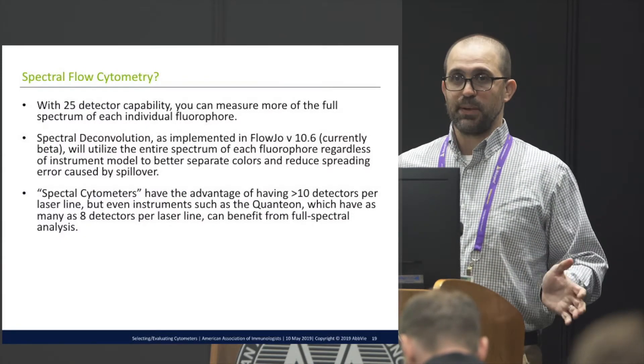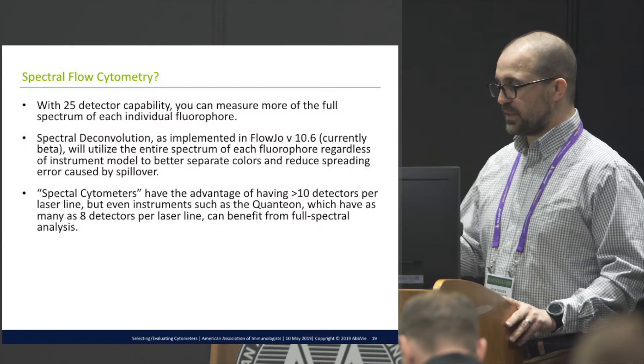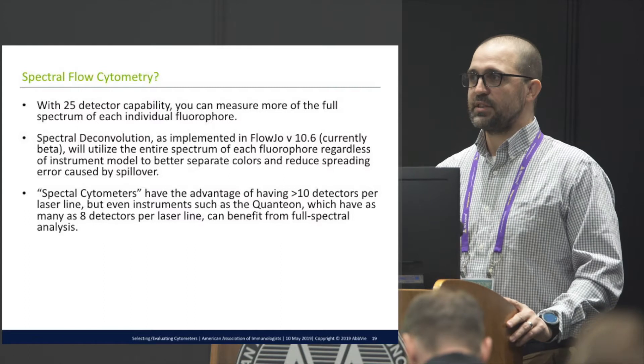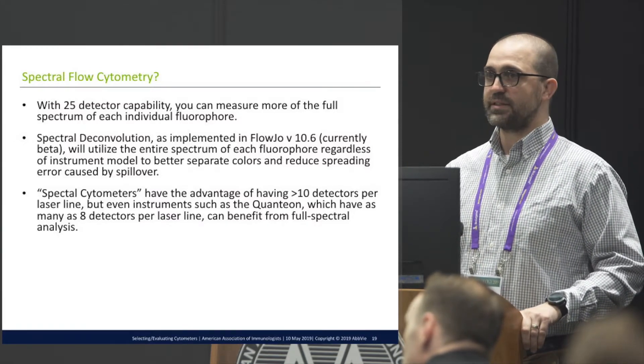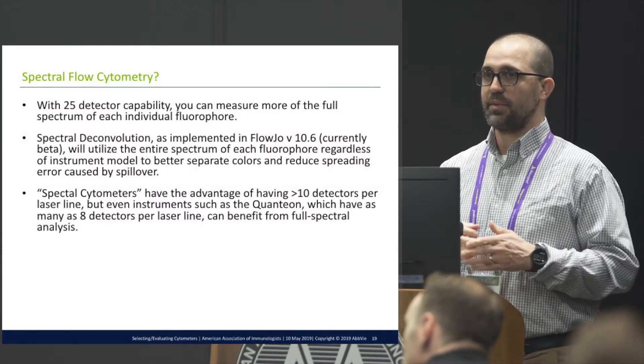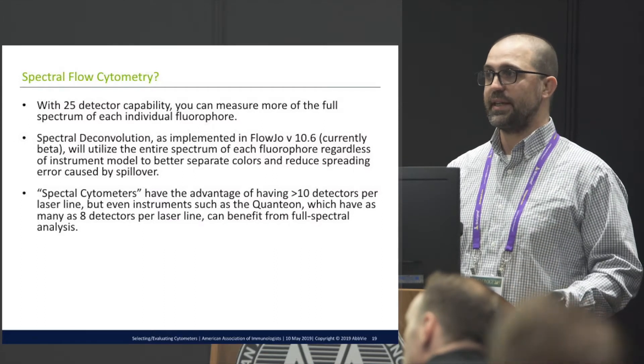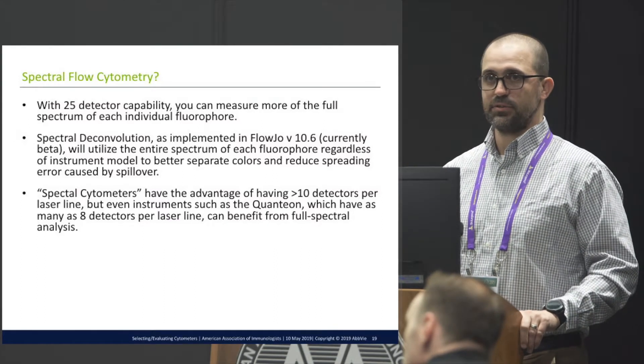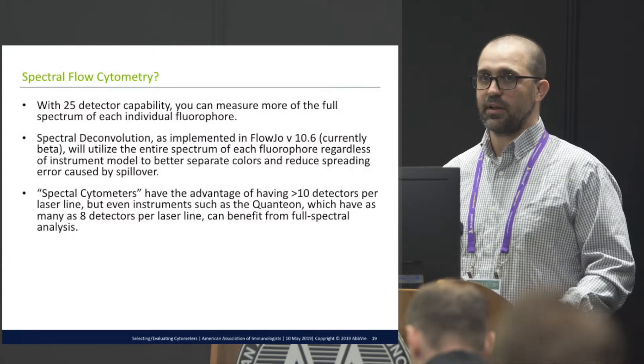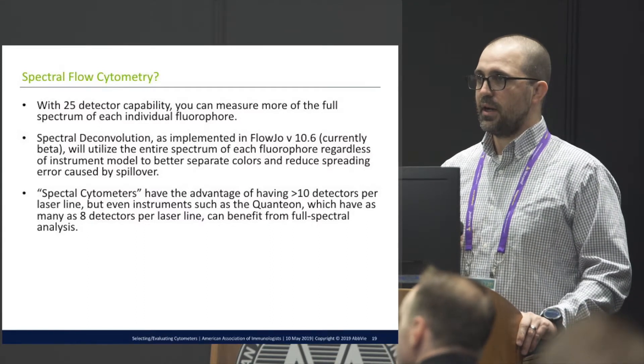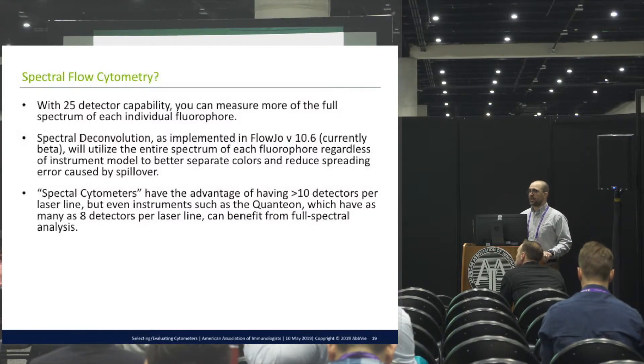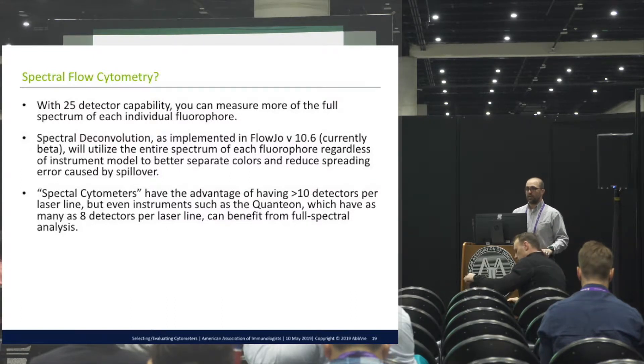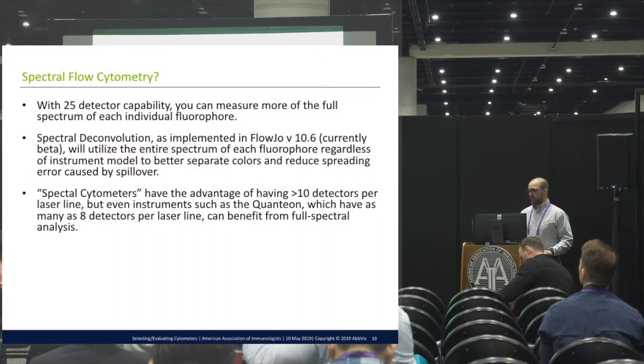I just want to mention something quickly about spectral cytometry. Everyone wants to do spectral cytometry, and the ability to do it is not necessarily limited to an instrument called a spectral cytometer. All spectral cytometry means is that you're oversampling the collection of photons from the full spectrum. So as long as you have a sufficient number of detectors on each laser, you can do spectral cytometry and spectral deconvolution. With the 25 detectors now on the Quanteon, if you're running only 10 colors, don't turn off channels you're not using — collect all light from every detector every time. By oversampling data outside the peak channel, you can use software to do spectral deconvolution.